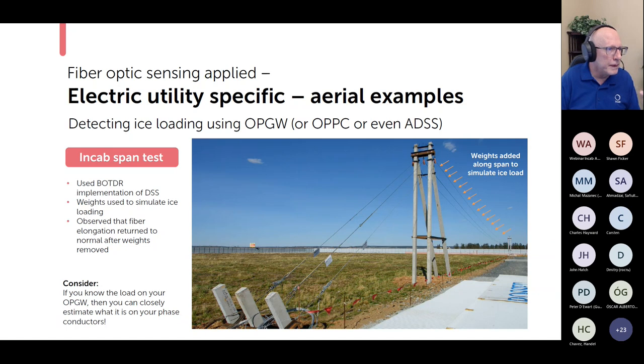That was incorporated into the design of this particular cable. And that same concept could be used with OPPC or even ADSS. But basically, when the fiber is under strain, you can detect the strain. When the loading goes away, the fiber returns to normal. And so it's excellent for detecting when you've got ice loading. And then consider, like I've talked about before, if you know the load on your OPGW, then you can closely estimate what the load is on your conductors as well.